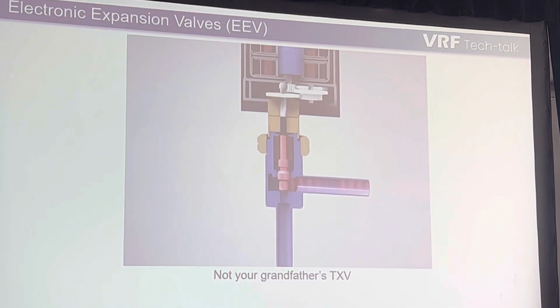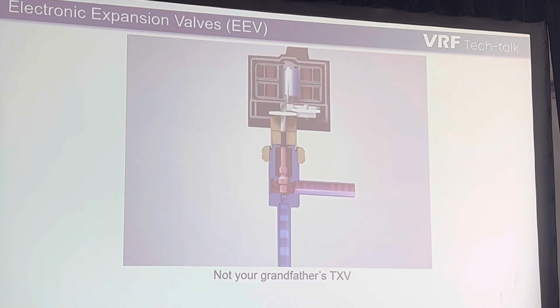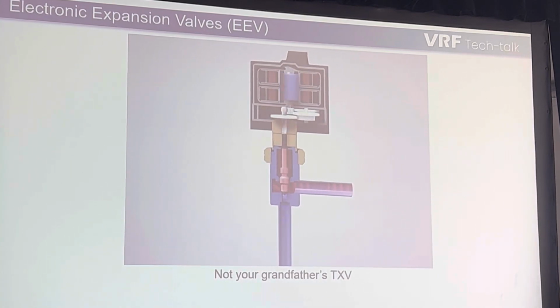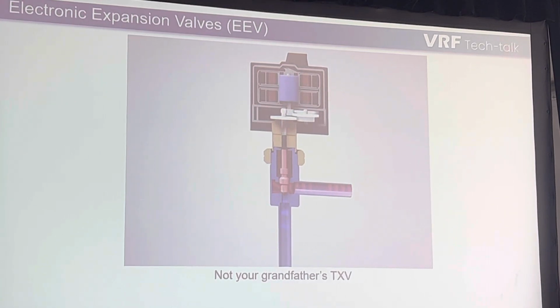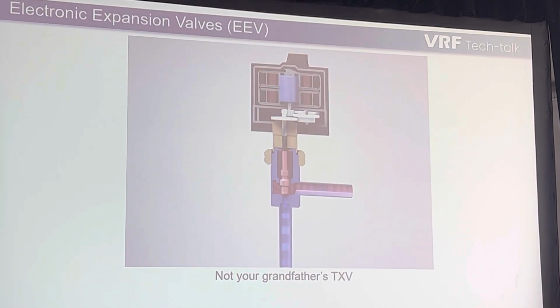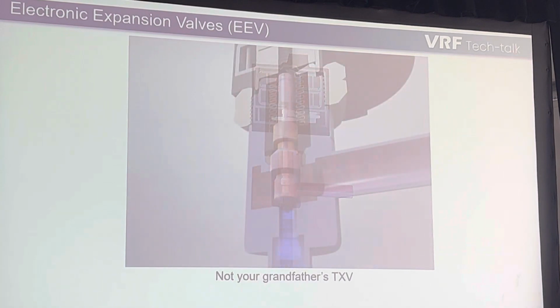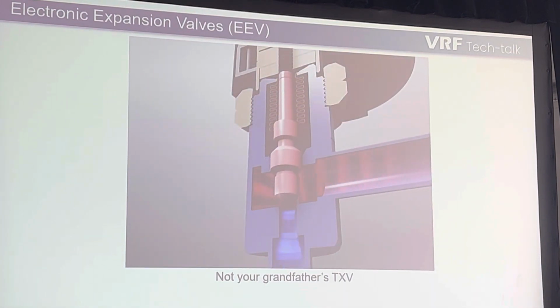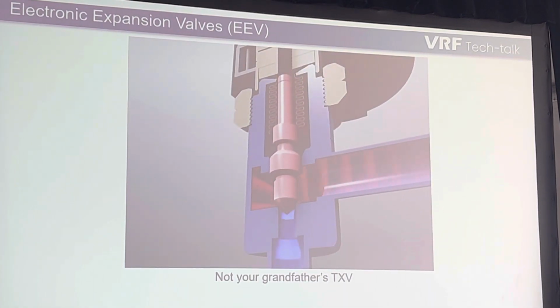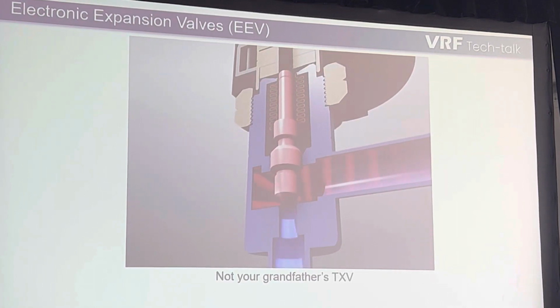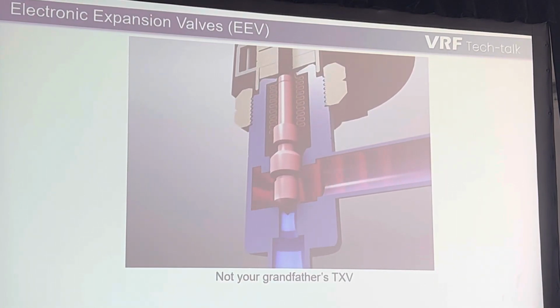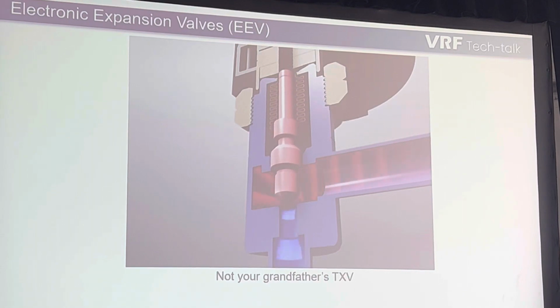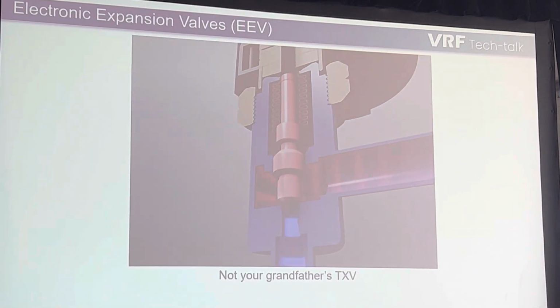If replacing these, is there a torque spec that we need to pay attention to? Yes, so it depends on the manufacturer. You can always find in the installation manual for certain components like this, or the service manual, positions as to where they want you to tighten it and direct it to, so that when it operates the 0 to 2,000 pulses, it's not overshooting or undershooting. But I would refer you to your specific manufacturer as to how they want you to install these, or the orientation of them on a particular piece of equipment. Because as you can notice, it's not centered, right? It's offset.